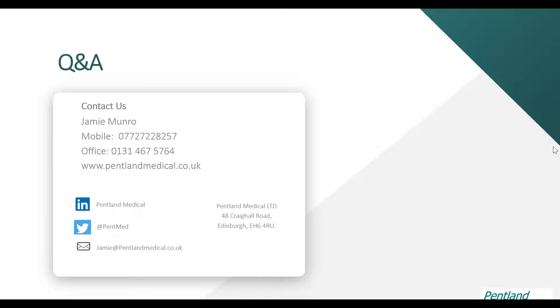Yes, again, a very good question. I would like to start by saying that people often forget that volumetric pumps are also inaccurate. In lab conditions, the average inaccuracy can be anything plus or minus 5%, and this can increase in ward settings. Now, Monidrop accuracy relates mostly to the gravity set accuracy, and that can vary from a few percent up to 10%. The standard says it shouldn't go over 10%, but there are gravity sets that are even more inaccurate than that. Monidrop's own accuracy is about 1.8%. So we tend to say to our customers that you can calculate the inaccuracy as around 11%, and then you know you're pretty much within safe limits.